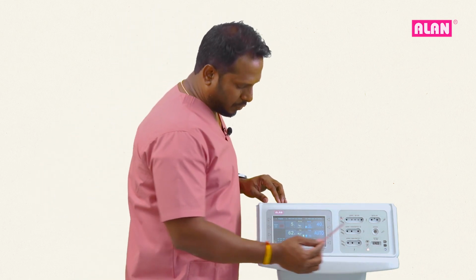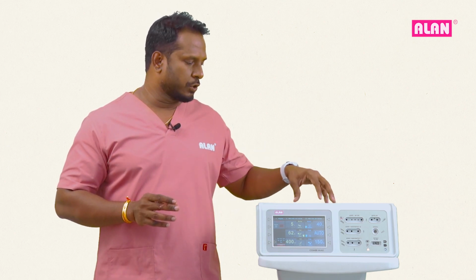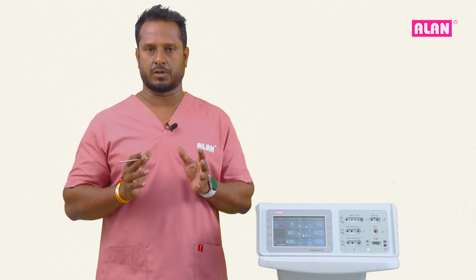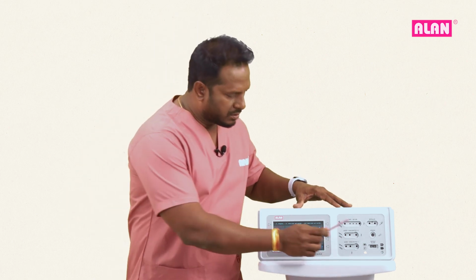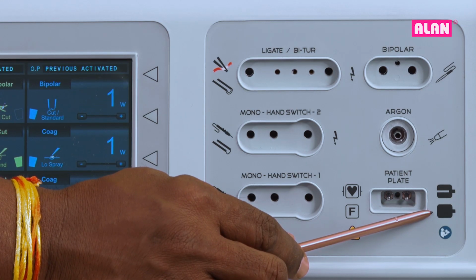In Combi Max, this patient plate receptacle is supported by an intelligent software called PPCM, which is the Patient Plate Contact Quality Monitoring System, to increase the patient's safety. What it does is check the contact quality between the patient and the return electrode. At any given point of time, if the contact reduces between them or it is not good enough, the unit does not deliver any output. Combi Max supports both split and non-split type of patient plate, whether they are disposable or reusable in nature.